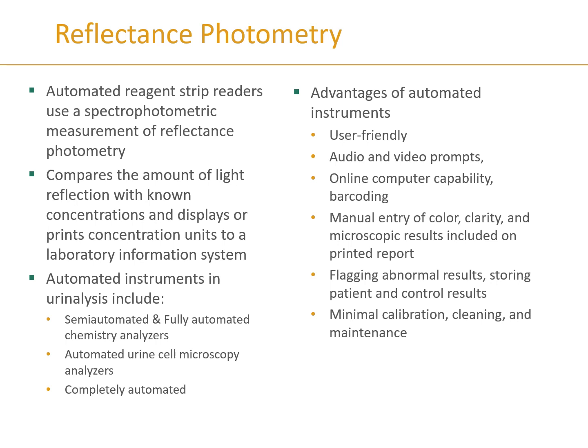Urinalysis automation uses reflectance photometry. With automated reagent strip readers, it uses spectrometric measurement of reflectance photometry, which compares the amount of light reflected with known concentrations and displays those concentrations in units on a printout. That can then be transferred to the laboratory information system, or LIS.